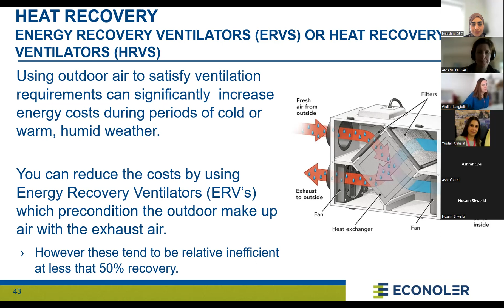We can also have wheels or other heat exchangers, and this recovery allows you, even if you have a high outside air demand because it's a very occupied building or a hospital, to still save energy by using this heat exchanger to preheat or pre-cool the outside air coming into your building. The system's efficiency can vary widely, but it's still very good to have because it helps greatly reduce HVAC consumption.